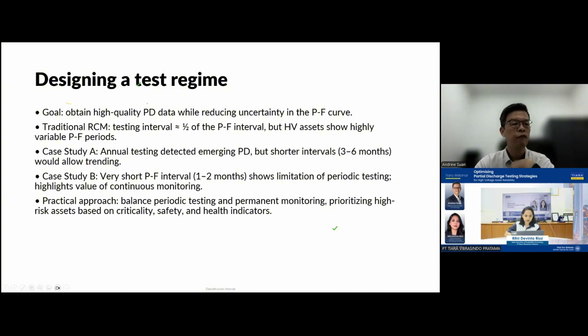Of course we say all this, but we also need to be practical. We cannot tell our people every day after lunch to go do a PD survey - it's not practical because my people aren't just focused on PD, they need to do other things too. So we must do balanced periodic testing, or consider installing permanent monitoring, especially on high risk assets - switchgear that you cannot afford to fail. Once it fails, a big portion of your production is impacted, or there are big safety issues. That's when you may want to consider permanent monitoring, because it detects PD every 2 minutes, telling you the problem straight away so you have enough time to react.